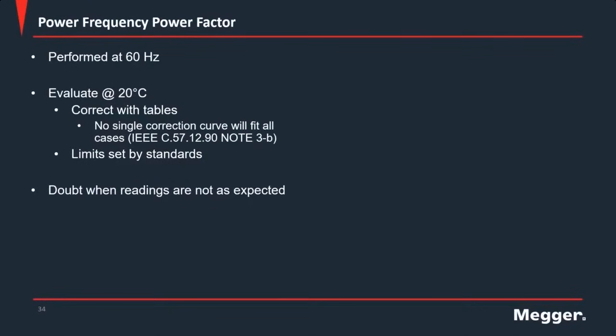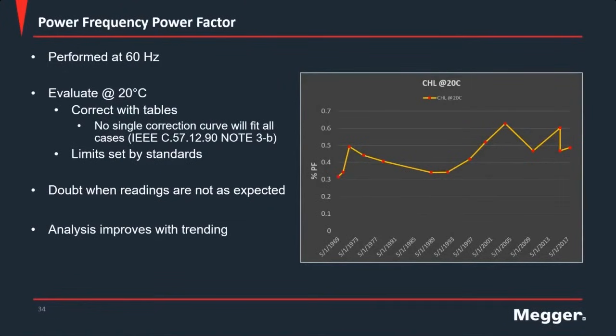So whether the value is a little bit higher or a little bit lower than the previous time, it's difficult to make conclusions on that. So what a lot of customers do is they will trend power factor data over time. But as I mentioned before, when we look at this graph of a transformer from high to low, we see that the power factor comes down from its initial highs in 1973 down to 1993, decreasing by almost 0.15% power factor. And if we know that insulation never improves, then what would be the cause for this seemingly improvement in power factor over time? And I think that it could only be contributed to incorrect temperature recorded at the time or incorrect temperature corrections used at the time.